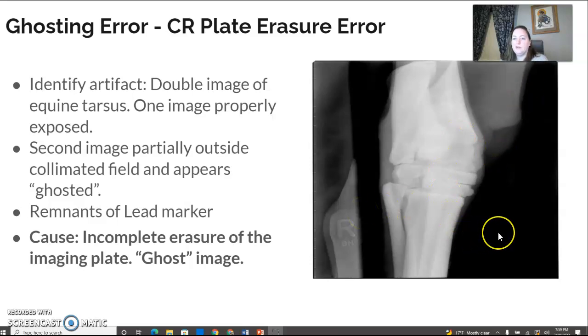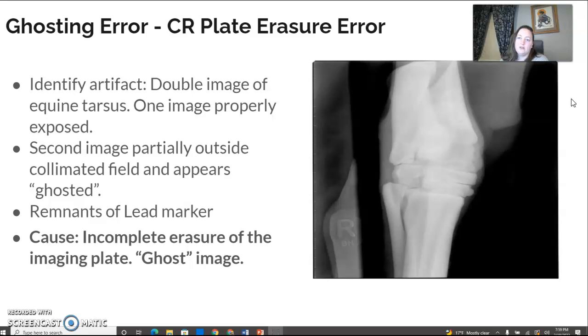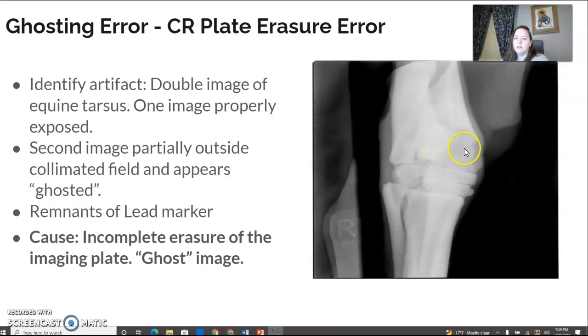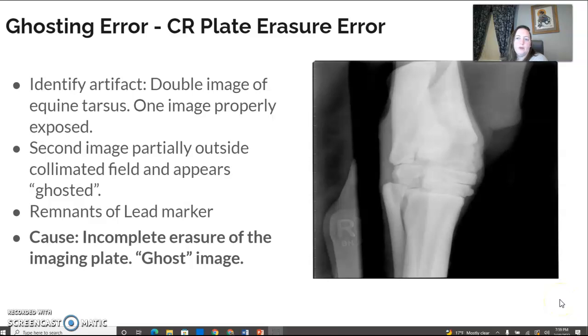If this happens to you, you're unfortunately going to have to repeat it. And if you do a big exposure, you have a big patient and you have to use higher technical factors, I would recommend erasing twice to prevent this from happening. Ghost error or ghost image is a CR error, and it's an issue with the erasing process, which uses a bright white light.